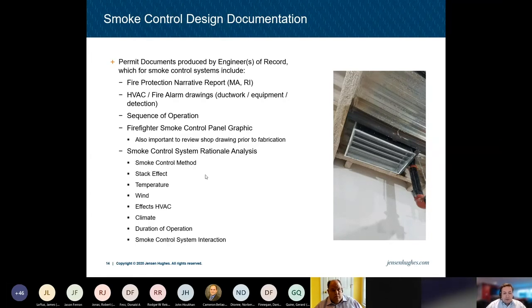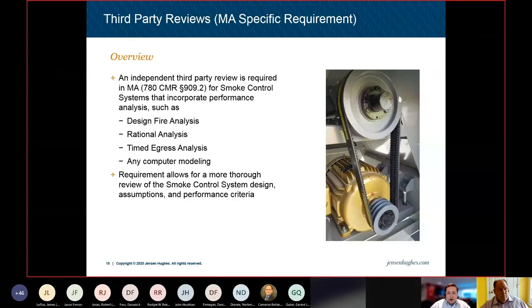And then the big item is the smoke control rational analysis. So that's the narrative that focuses on the smoke control system. It gets into the smoke control method, talks about stack effect, temperature effects, wind effects, the effects of normal HVAC operation on the smoke control system, effects of climate on the equipment. So, if you have a detector outside for the HVAC, say a stair pressurization fan, is it listed for the ambient conditions? And it talks about the duration of operation of the system and then the smoke control interaction with the building. So right now I'm going to turn it over to Dave, who's going to get into some third-party reviews, talk about special inspections, and is also going to get into routine testing, once the system's commissioned, what's required during the life of the building.